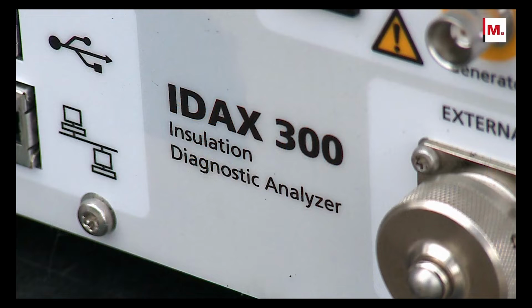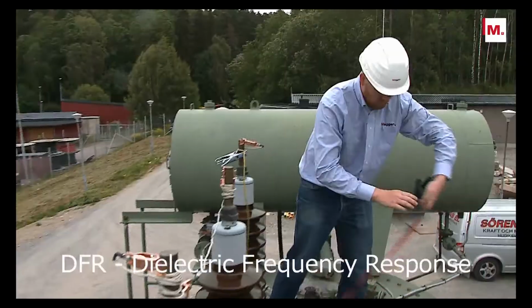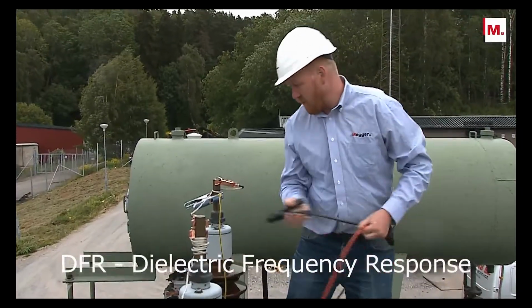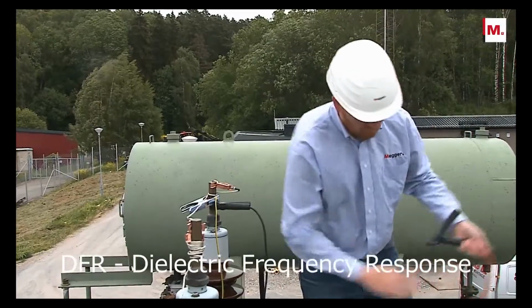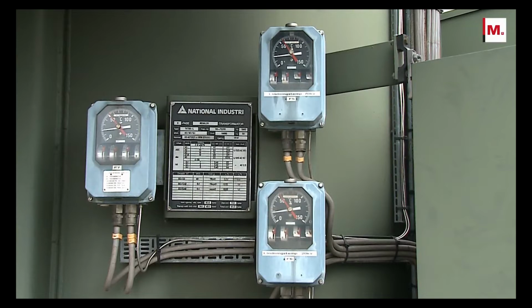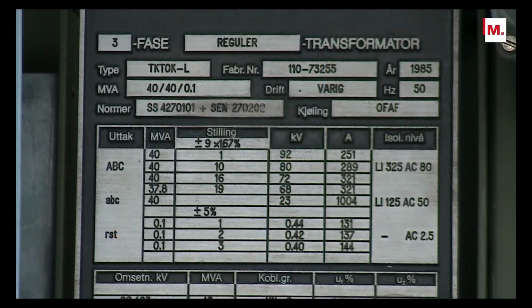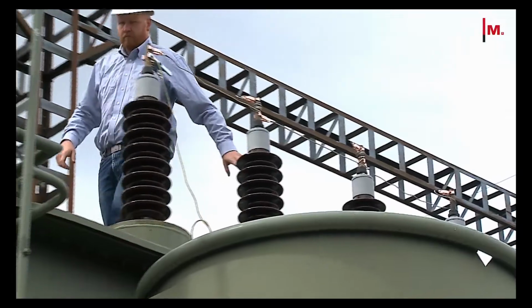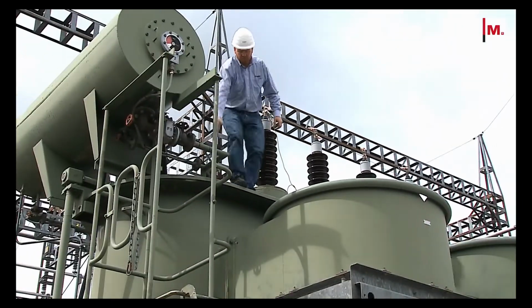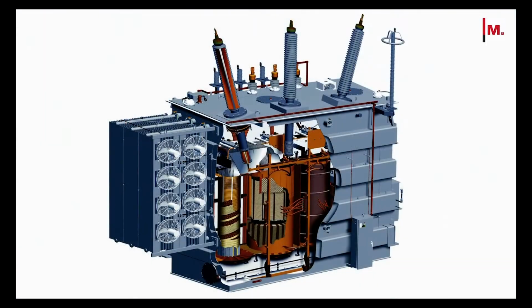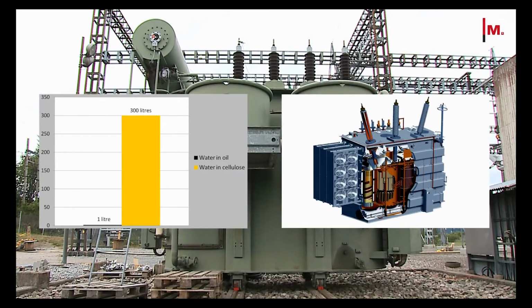Dielectric frequency response measurement, DFR, is a cost and time-effective method to determine the health of the transformer, including the moisture content of the oil paper insulation system. It's important to understand that almost all the moisture in a transformer is in the paper, not in the oil. Typically, more than 99% of the moisture in a transformer resides in the cellulose insulation. Therefore, the traditional method of inferring cellulose moisture content by measuring water content in the oil is much less accurate than using DFR measurements to calculate moisture in the cellulose.